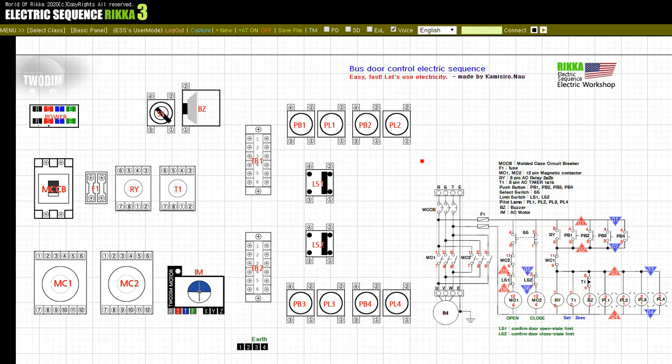Look at the electrical sequence configuration on the right side of the screen. In the main circuit, there are two magnetic contactors MC1 and MC2 below the wiring breaker MCCB. The magnetic contactor MC1 rotates the motor in the forward direction and opens the bus door during operation. MC2 rotates the motor in the opposite direction and closes the bus door during operation.